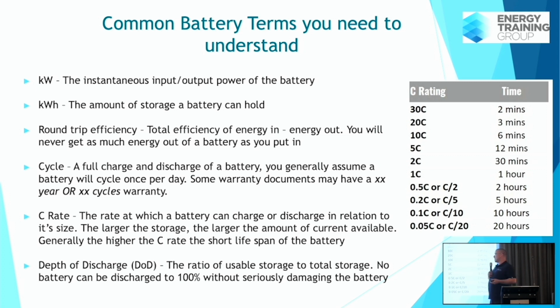With lithium, you're discharging down to 90 to 95%. However, if a lithium battery does discharge to 100%, same thing, it's still cooked, it's going to go in the bin. Mostly batteries won't allow you to do that - they've got a BMS on board, and that BMS is going to trip out. It's not going to allow the battery to deep discharge. Some of the initial batteries released onto the market a few years ago did have an issue where they would overload, particularly the LG Chem batteries. But largely that seems to have been solved by most manufacturers now, and I'm not seeing depth of discharge issues out in the field anymore.